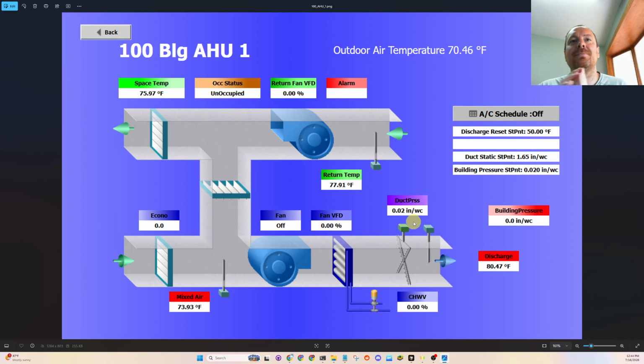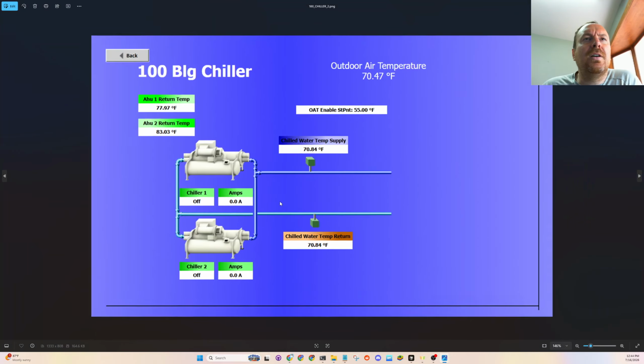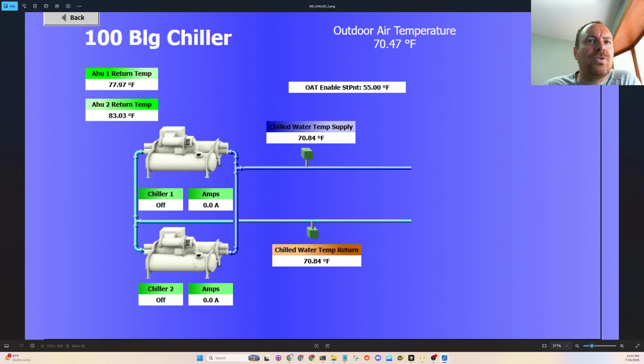That's where I'm seeing the energy saving strategies: Guideline 36, duct static pressure control, discharge air temperature reset. And to do all that, we need a fully functional 100% removal of the pneumatic system. And we can talk about that more in the future. And then I think these chillers would be decent sized air cooled chillers too. That this enable set point is also something that we could bump up to 60.